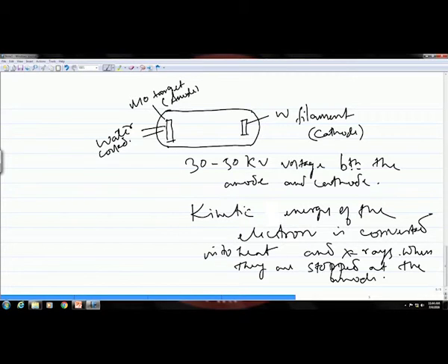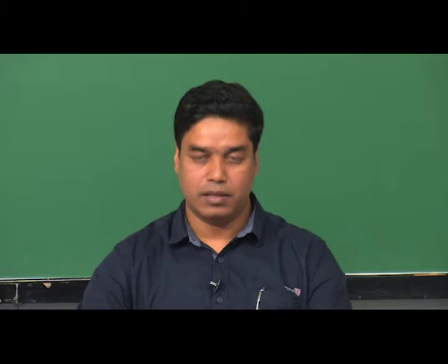Right. So, this is how X-rays are generated. This is basically an X-ray tube which is maintained in vacuum, and the main components of this tube are these two electrodes, the tungsten filament cathode and the molybdenum anode, and then you have to maintain this high bias between the anode and cathode, and then you can generate these X-rays by this energy conversion.